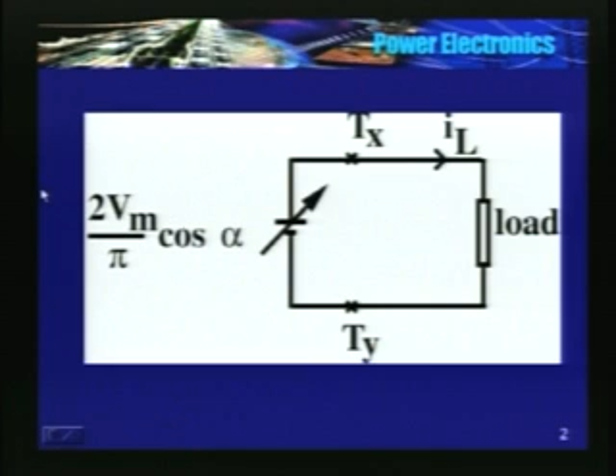So we used only one converter wherein voltage is reversing but the current cannot reverse. So we will use one more converter connected back to back, in the sense current can flow back to the source through the second converter. So there are two converters, hence the name dual converter. If you see converter 1, voltage can be positive or negative, current is always positive. So operation is in quadrant 1 or quadrant 4.